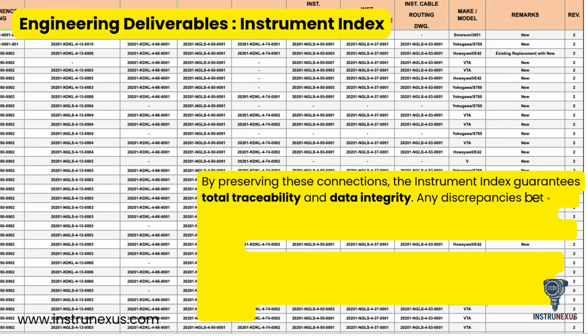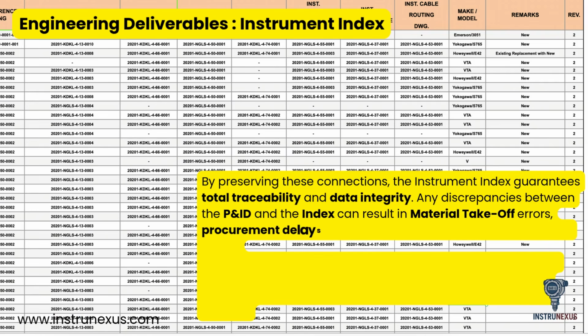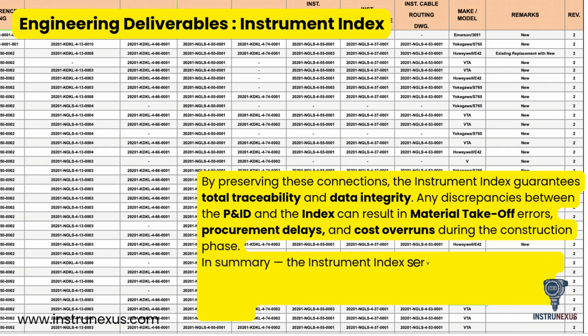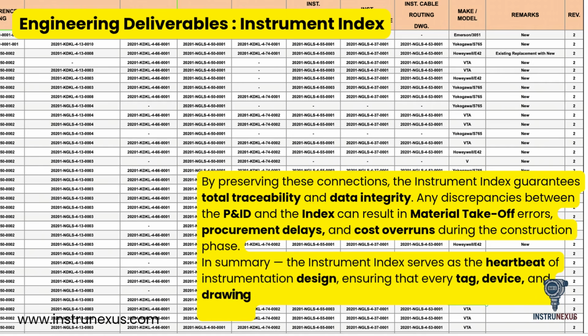Any mismatch between the P&ID and the index can lead to material takeoff errors, procurement delays, and cost overruns during construction. In short, the instrument index is the heartbeat of instrumentation design, ensuring that every tag, device, and drawing remains perfectly aligned across the project lifecycle.